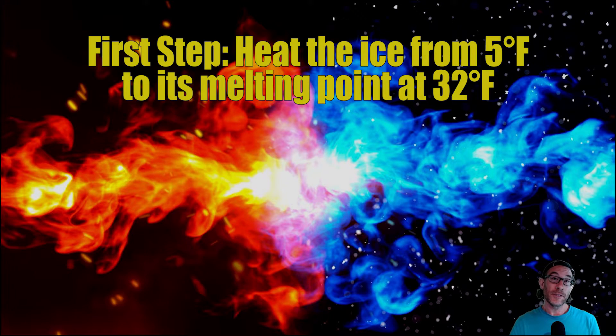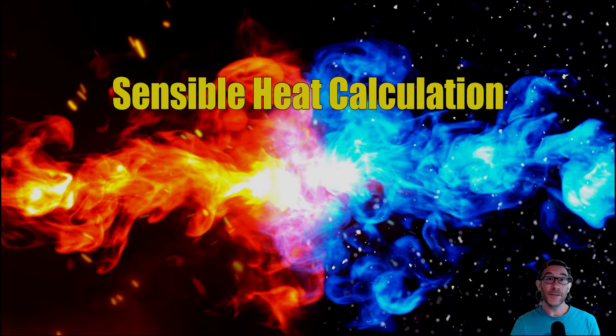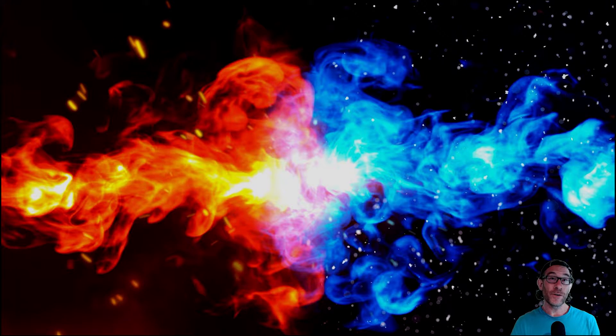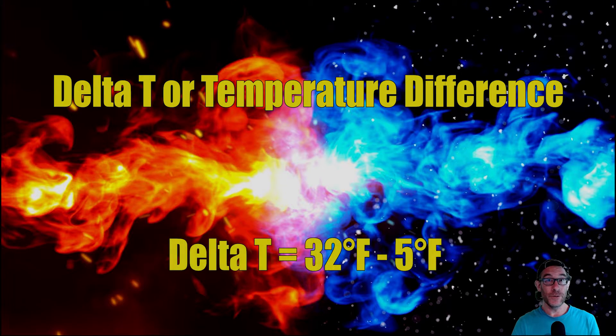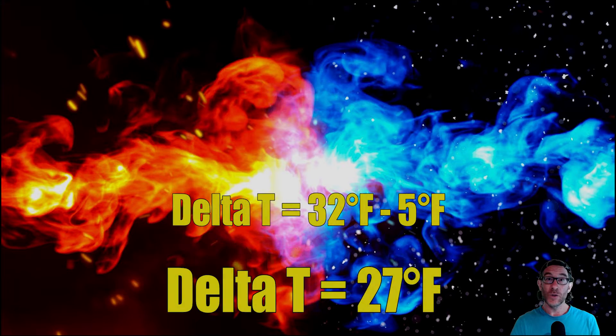First step: let's take this block of ice, which is at 5 degrees Fahrenheit, and heat it up to its melting point at 32 degrees Fahrenheit. This is a sensible heat calculation. First, we need to figure out the delta T, or the difference in temperature. So I take 32 degrees Fahrenheit and subtract 5 degrees Fahrenheit — I need to heat up this block of ice 27 degrees to get it to its melting point.